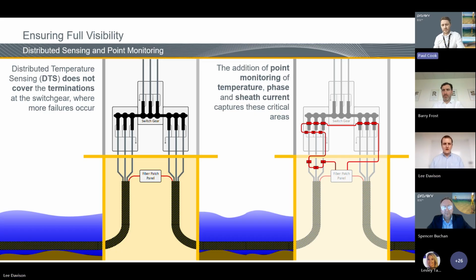I think it's also worth sharing with the audience that the implementation of this technology, particularly the DTS element and point monitoring for temperature and current, these are passive sensors in that they don't have to be powered - there's no additional power infrastructure needed, and no additional telecoms infrastructure required to get the data from the sensing source to the interrogator, which processes the data. It's all based upon photonics, light through fiber. So there's no additional equipment other than the sensor itself to be deployed, whether around the three phases, the earth sheath, or monitoring the termination connections for thermal measurements.